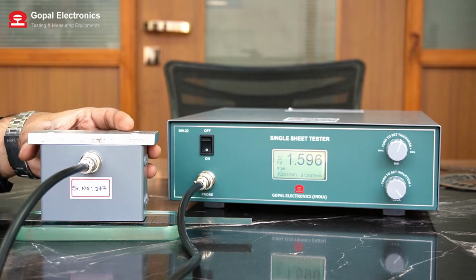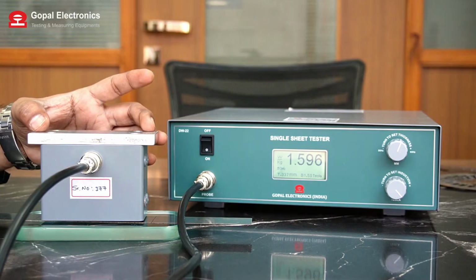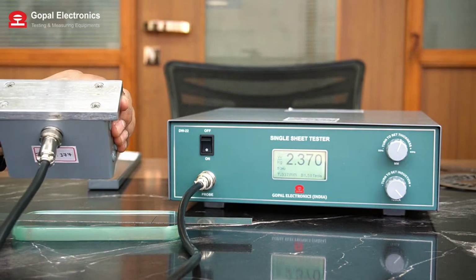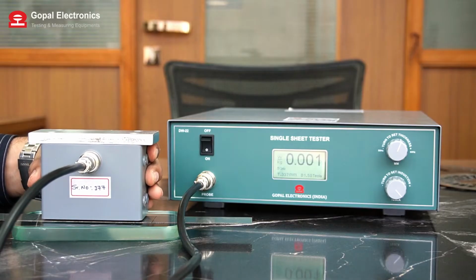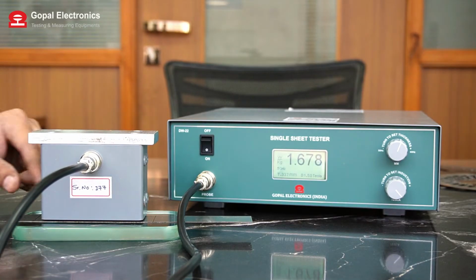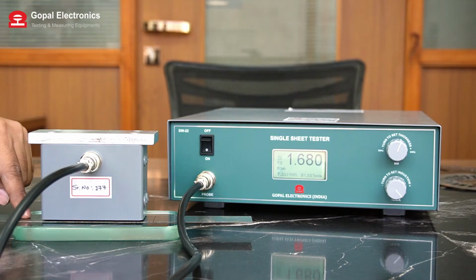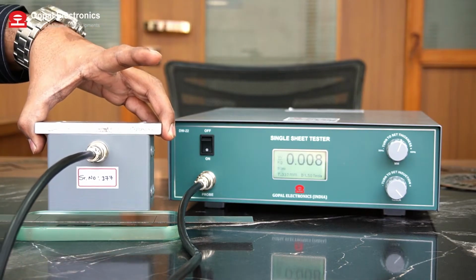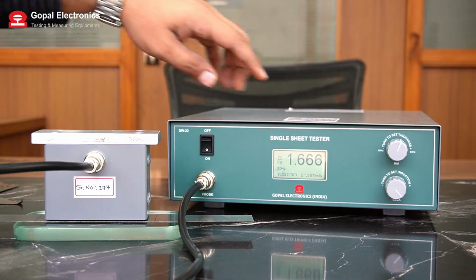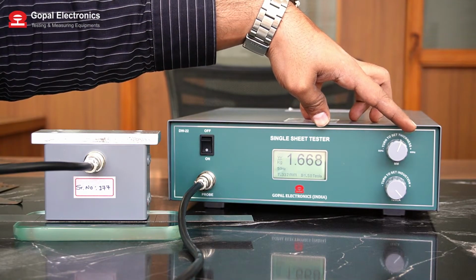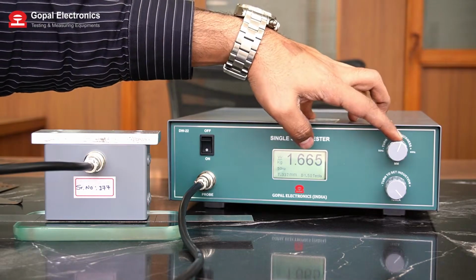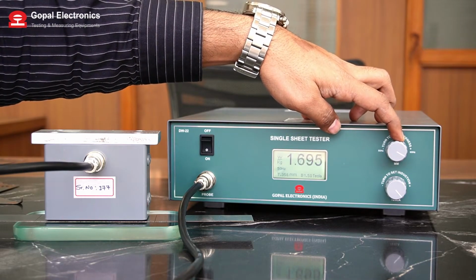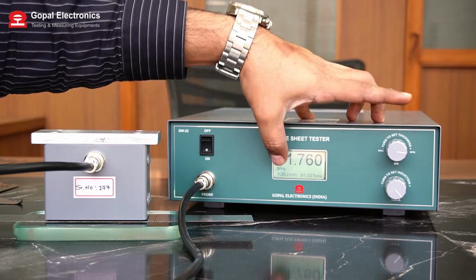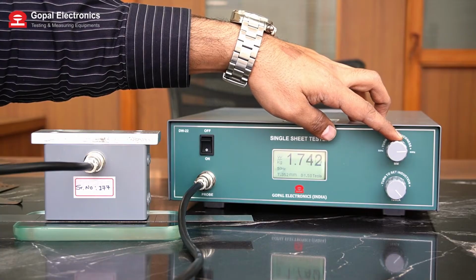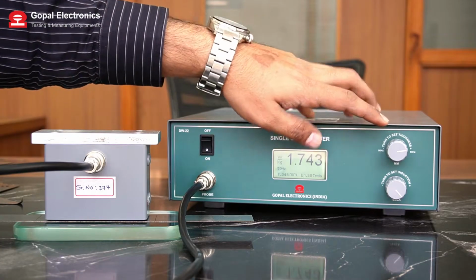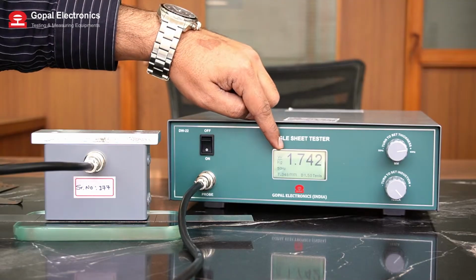Here you can check, we have provided one probe and the weight is pre-fitted through this screw, so it will be sturdy. Whenever you place it on the sample, it will not move. First you have to use a glass surface, then you put the sample, and then you have to place the probe on the sample. Now you have to set the thickness. Right now our sample is 0.35 thickness, so you can set through this knob. 0.35 I am setting. You can check on the display right here. Induction we are testing at 1.5 Tesla, so this is the reading of this sample.